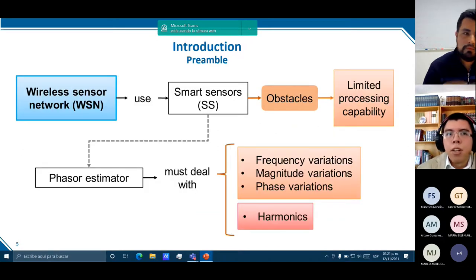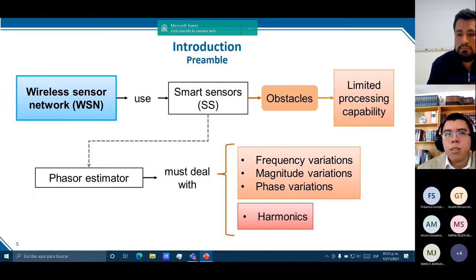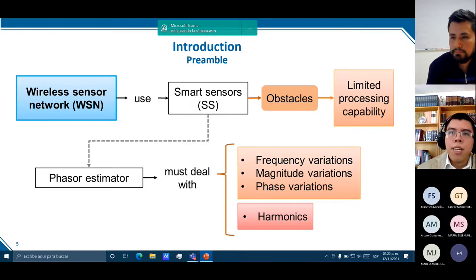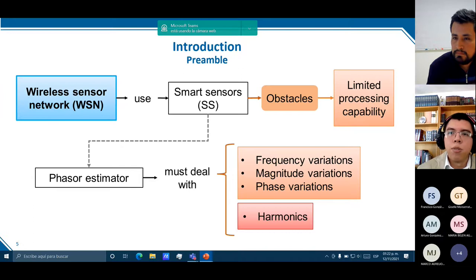However, this system has problems mainly in economic terms due to the high cost of PMUs and the need for wired communications, which further raise installation and maintenance costs. A low-cost alternative is the development of wireless sensor networks, which have advantages like rapid deployment, flexibility, and aggregated intelligence. The main components of these networks are the smart sensors, which perform the phasor estimation process; due to their limited processing capability, they require low computational load algorithms. The phasor estimator must also deal with frequency variations, magnitude and phase angle variations, and harmonic contamination, while complying with the IEEE standard for synchrophasors.